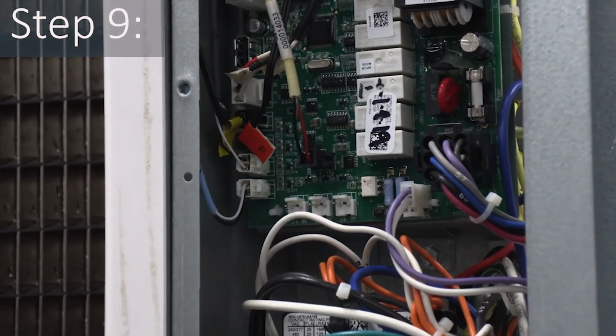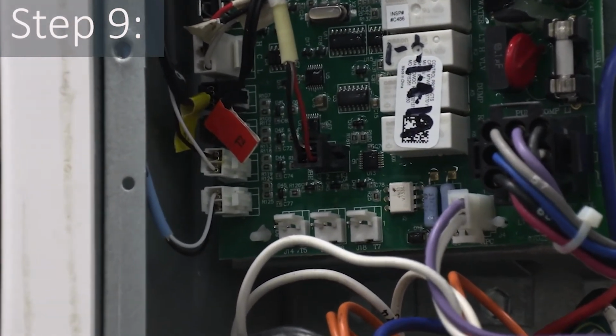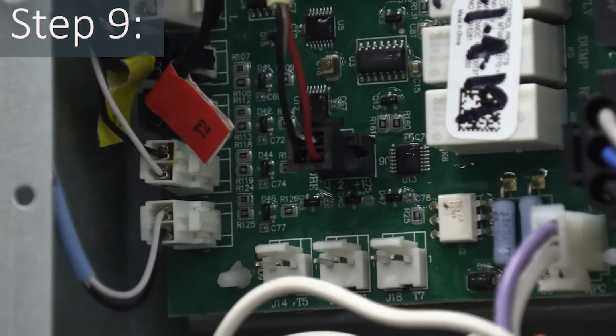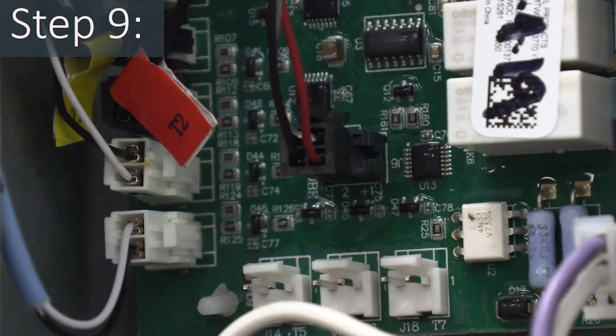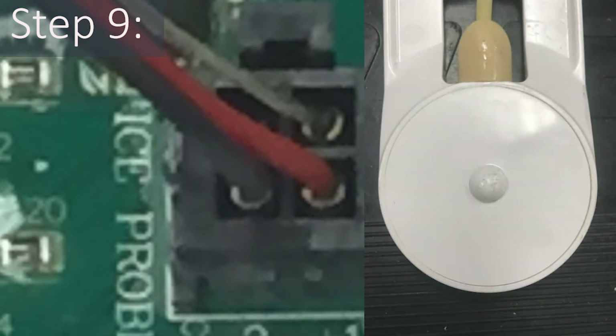tap test, verify the ice thickness probe connector is properly plugged into the board and the wiring is in the correct positions with the plug. With the connector plugged into the board, the top left position should be blank, the top right position should be the twisted ground wire, the bottom left should be the black wire, pin number 2, and the bottom right should be the red wire, pin number 1. If the wiring is incorrect, replace the ITP.